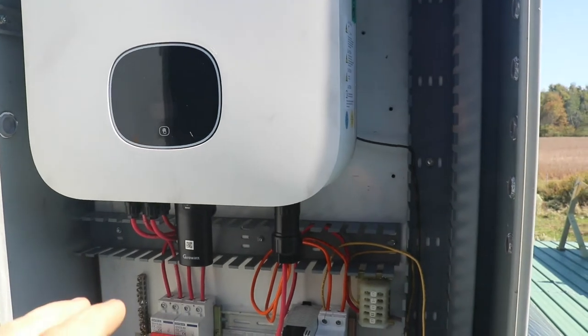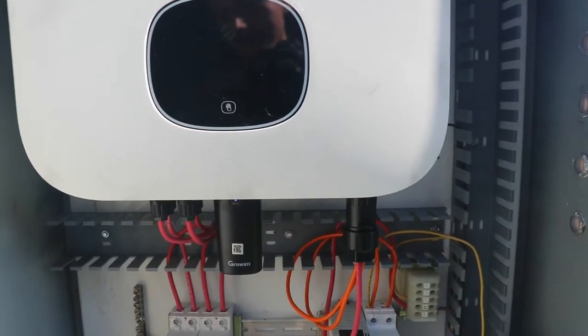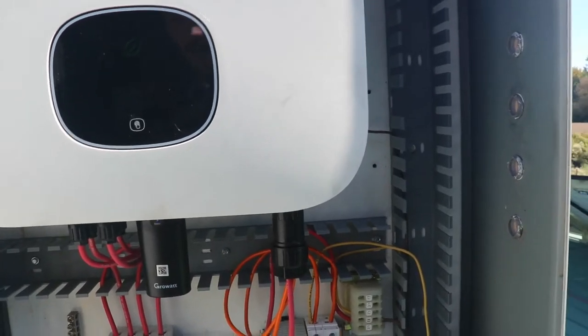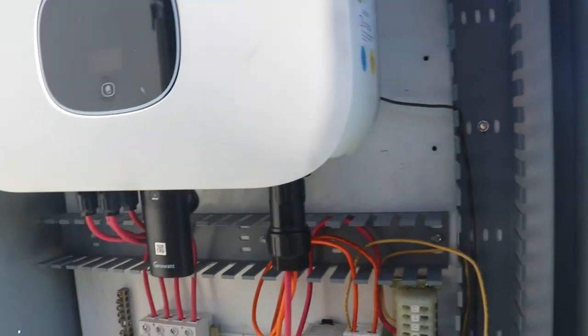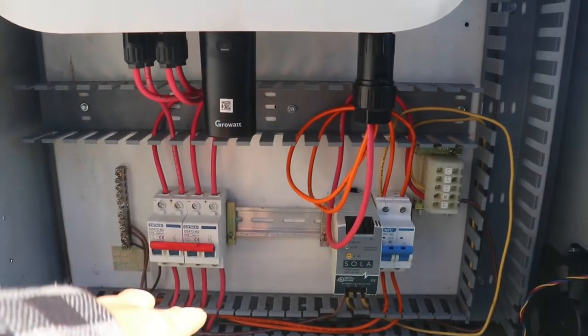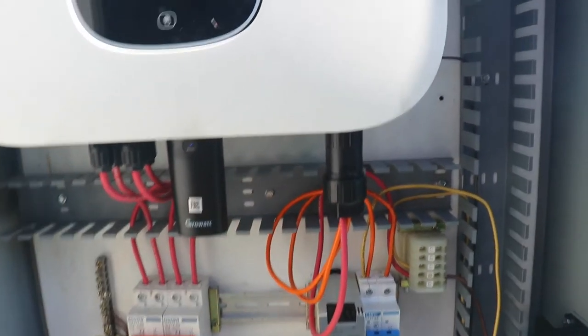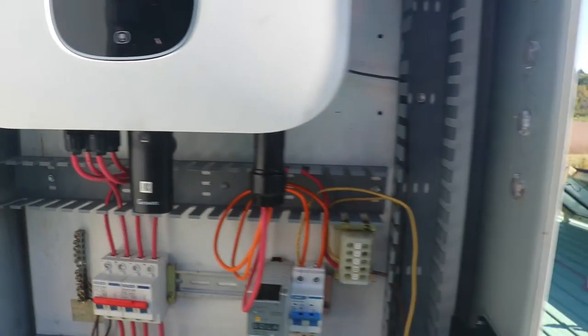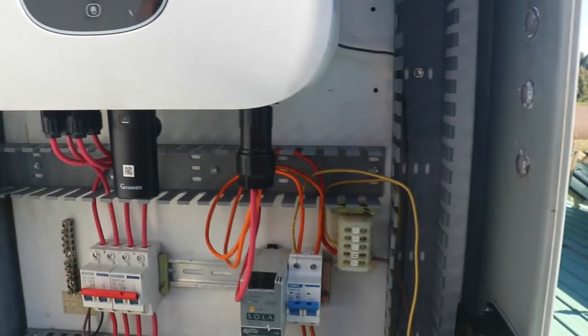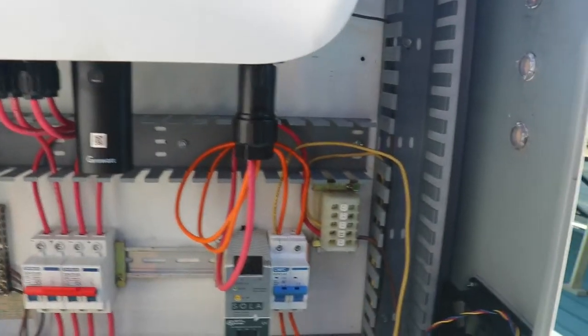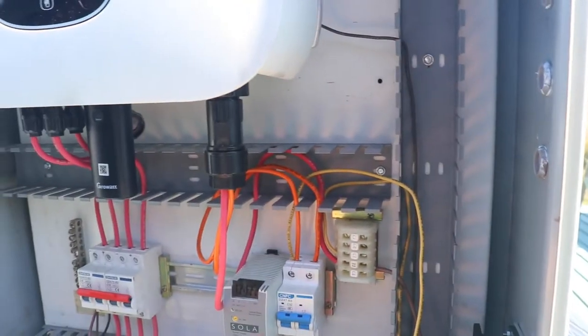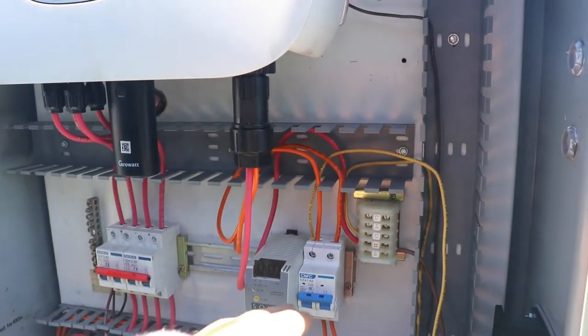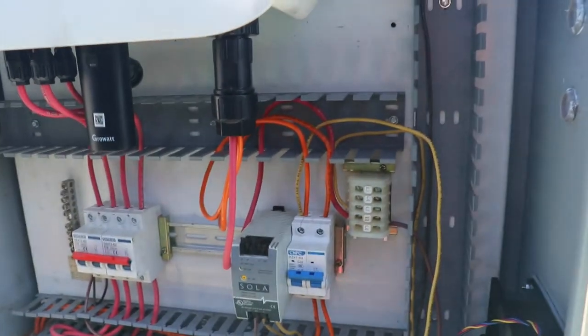Down below I have some DC disconnect breakers. Make sure when you put your disconnect breakers, if you're trying to switch DC, it's very important that you are using DC breakers and not AC, because DC is like at least 10 times more likely to arc, especially with this system. With this system under load it's about 450 volts roughly, open load is almost 600 volts. That is very very easy to arc.